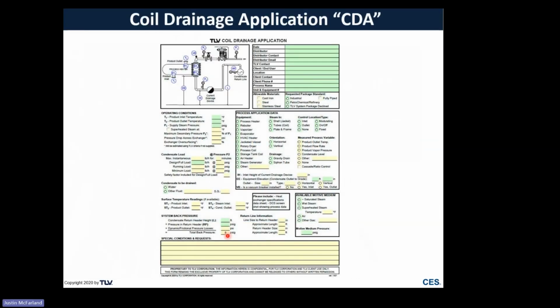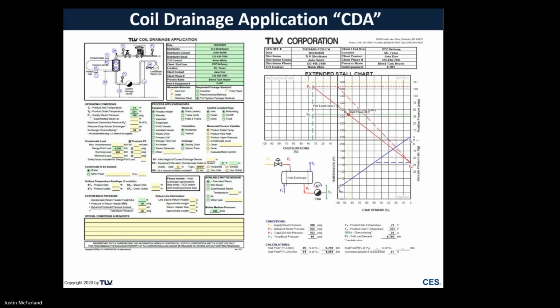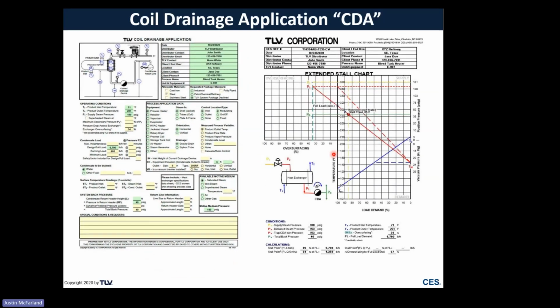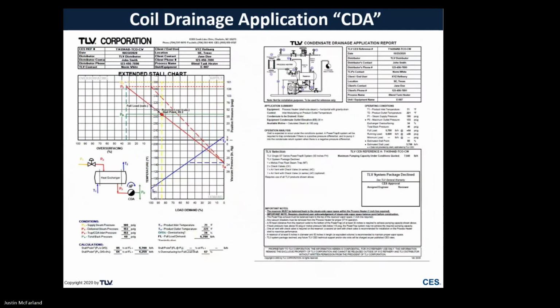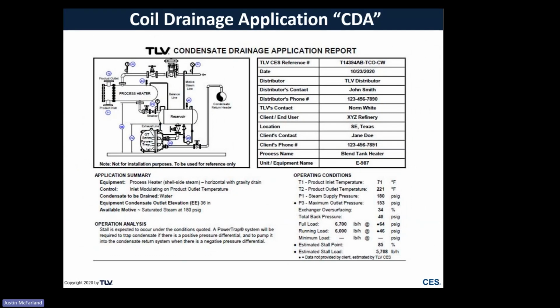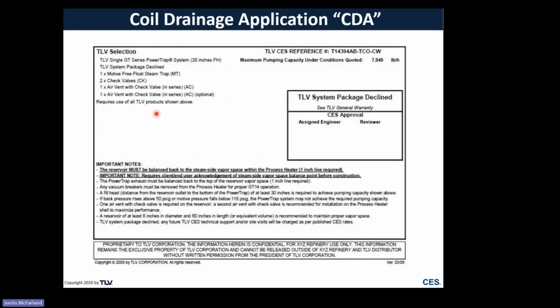So getting into, well, how do we size this? What does this look like? TLV has developed a form. I know everybody just absolutely loves forms. TLV loves forms, but it's a way for us to collect all the critical information so that we can size the power trap system for you. So once you've got all the green areas filled in, what we're going to do is create that stall chart for you. We're going to show what our estimated stall point is. And then based on that analysis, we're going to make a recommendation. Say, hey, this piece of equipment appears to be in stall, and here are all the operating conditions you gave us. Here are our recommendations with a nice little sketch. Here are other product recommendations and some really important notes that we think you need to pay attention to.